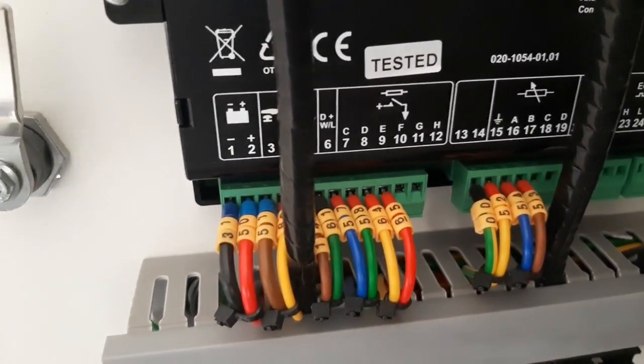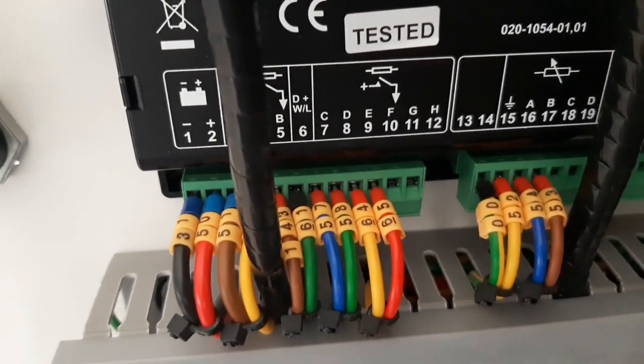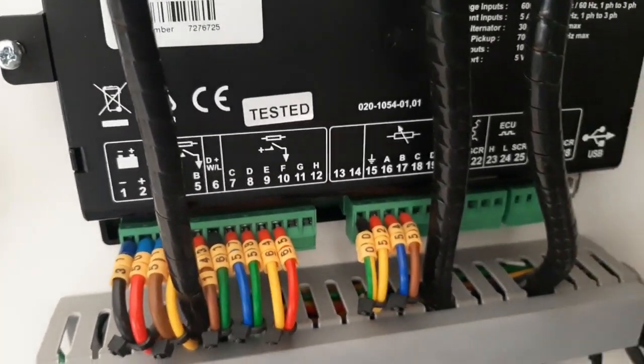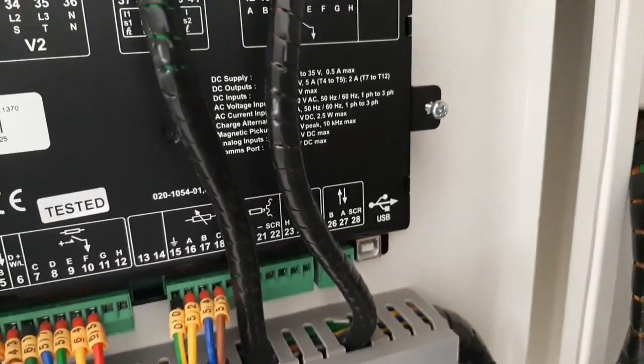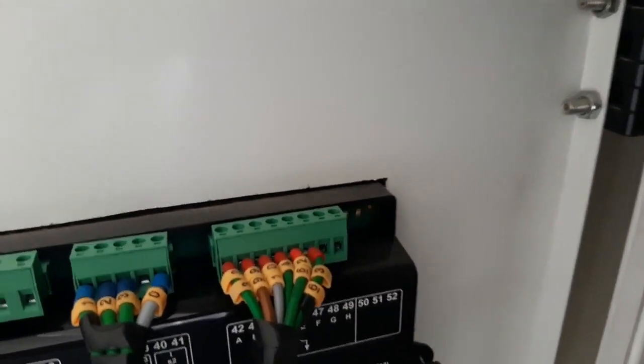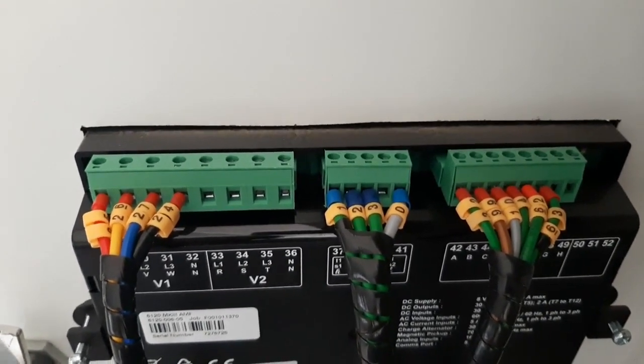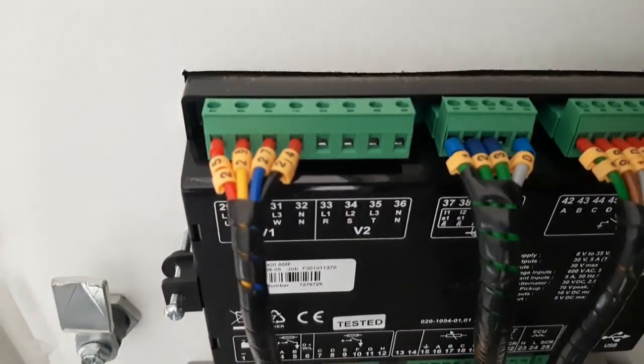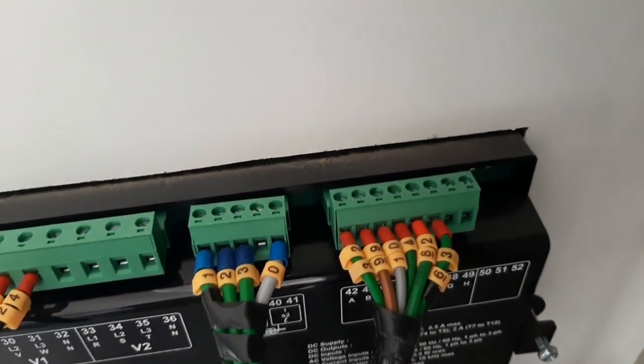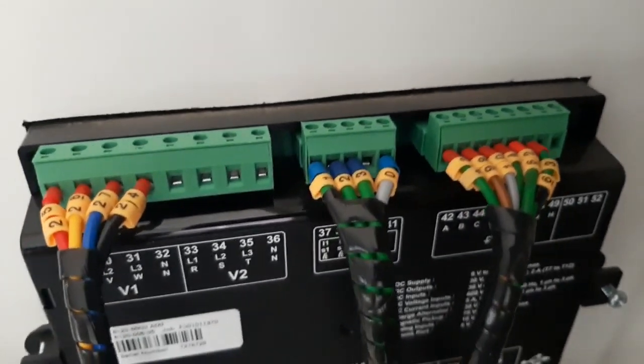On the back of the module: number one is the negative of the battery, number two is the positive, number three is the emergency push button. Numbers four and five are digital outputs, then DW is for the dynamo, and from number C to number H these are digital outputs. Further up, all these connections are digital inputs. V1 and V2 are generator alternator voltage sensing contacts. Terminals 25, 26, 27, and 24 — these four are from the generator and these four cables are from the CT.